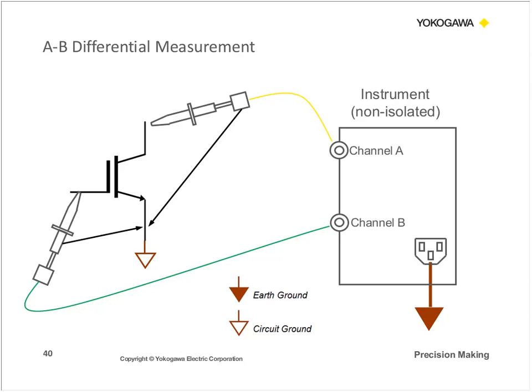This is the case because when the common mode voltage is greater than the differential voltage, you're not going to be able to detect that change. Both probes are going to read the same if you have a very high common mode voltage and you're trying to measure a low differential voltage. You also have to remember that this technique is a math-calculated measurement, so it's not a true measurement, and you're not going to get the guaranteed accuracy that you're looking for.